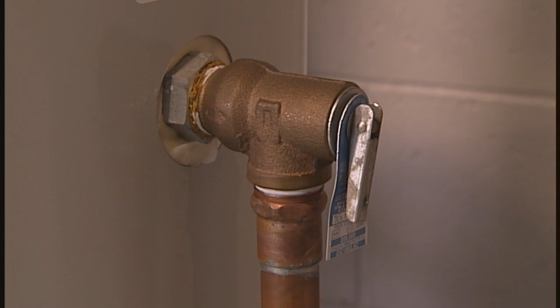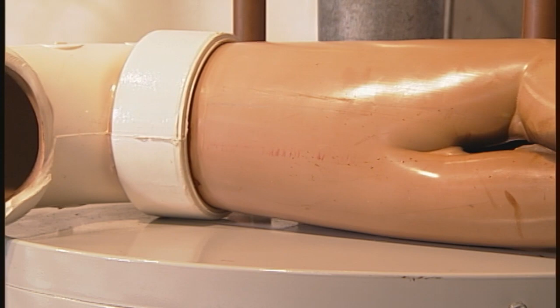And unfortunately, a lot of homeowners think they can just run down to the hardware store or the big box store, pick up a water heater, and install it themselves. But judging by this vent, this is what can happen if you do it incorrectly? That's correct. You'd never want to stick PVC pipe on a B-vent water heater -- it's strictly made for a power vent water heater.